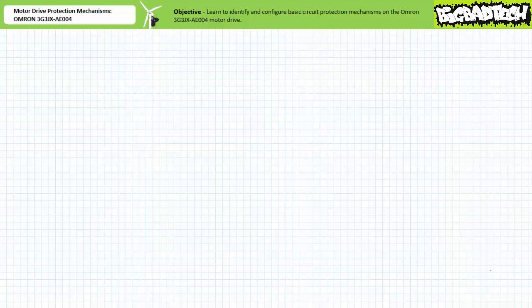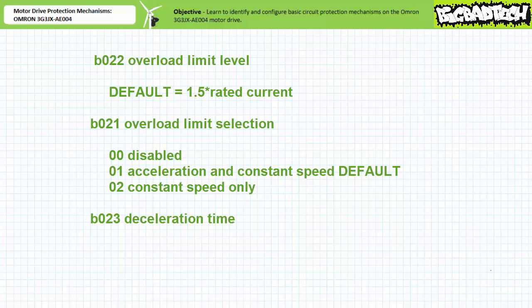Given a motor drive can vary both applied voltage and excitation frequency, this seems an elementary method of self-correction. However, the deceleration event designed to correct the overload needs to be carefully coordinated not to interfere with the application. This active overload limitation response is configured using three protection parameters. The first and most important is B022, the overload limit itself — the cliff edge beyond which drastic measures need to be taken. The other two are B021, overload limit selection, and B023, deceleration time.